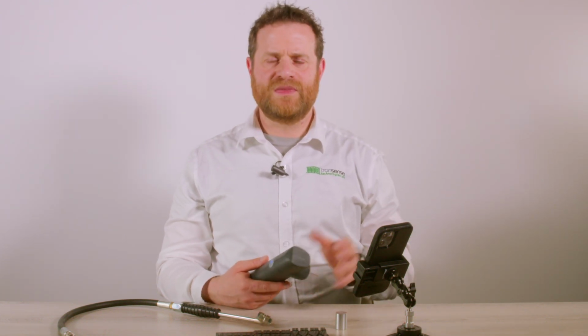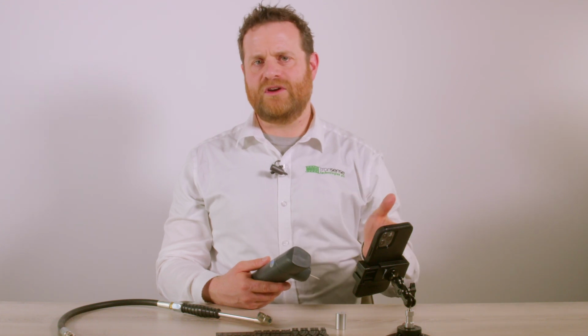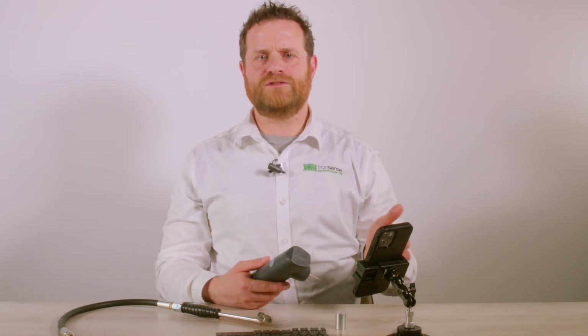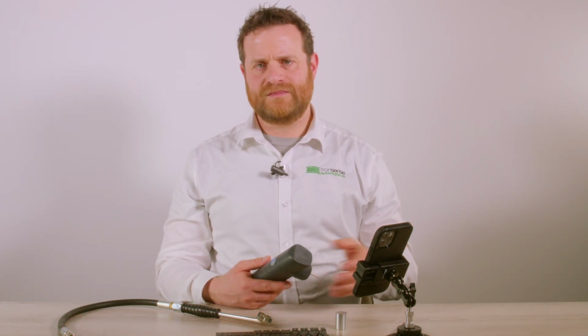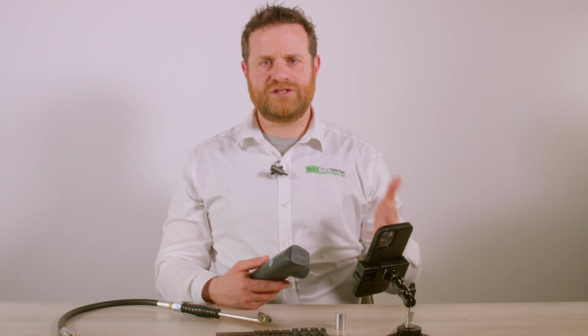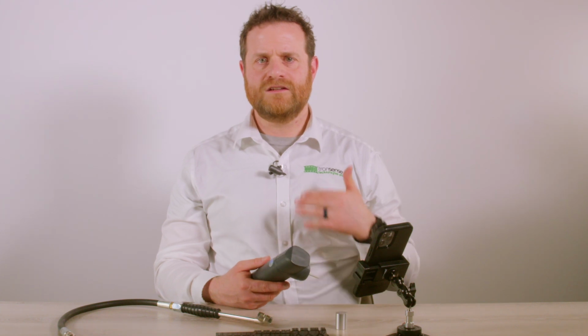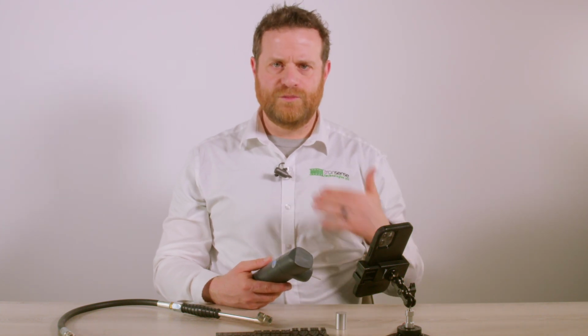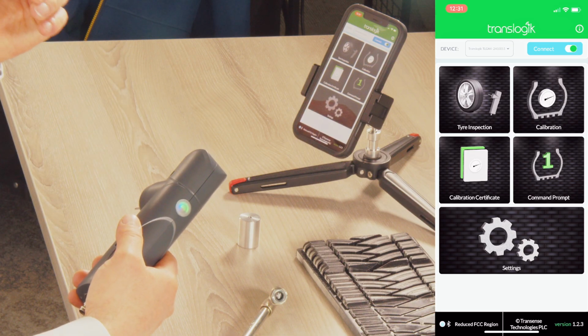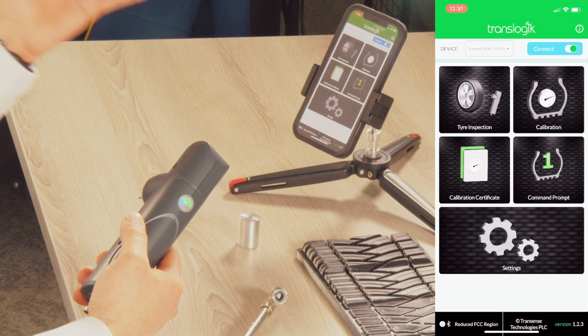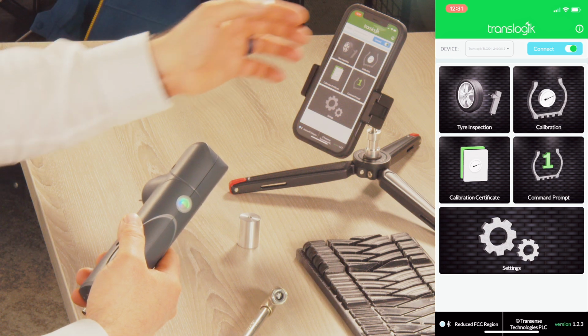TLGX tools are delivered calibrated from our production facility. The user may choose to recalibrate the depth measurement gauge of the tool using QuickCal. Calibration of the pressure function is not possible by users in the field. Contact Transense for more information on pressure calibration. To calibrate the depth measurement gauge, select Calibration and then follow the on-screen instructions.